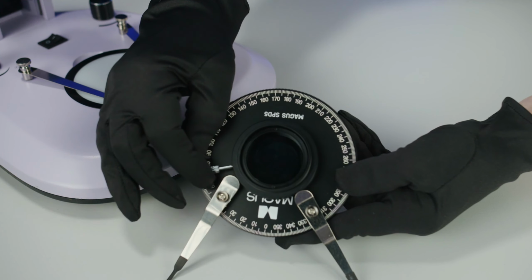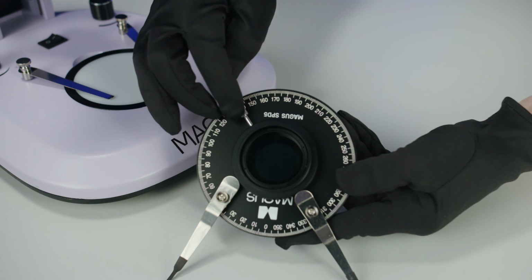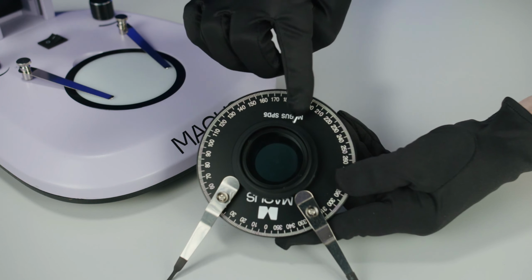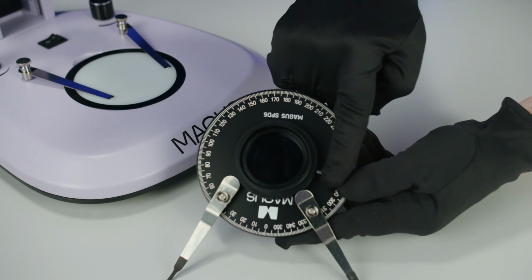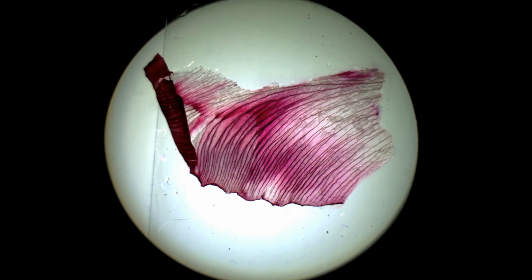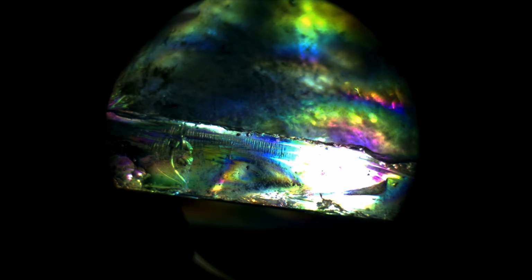By changing the relative orientation of the polarizer and analyzer, the intensity of the light can be controlled. When positioned perpendicularly, a complete darkening effect is achieved. In this position, the device for simple polarization reveals internal features of the sample that are not visible in bright field.